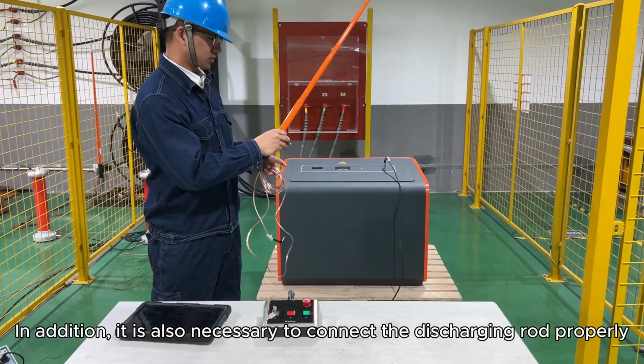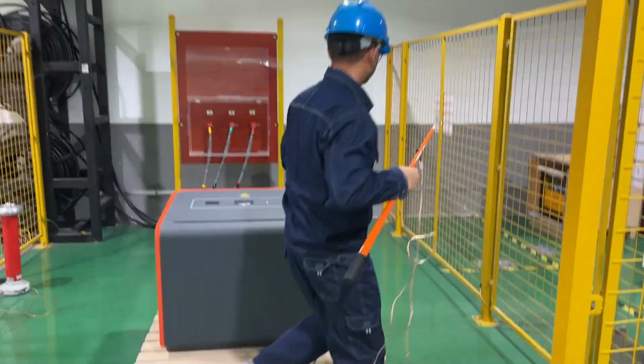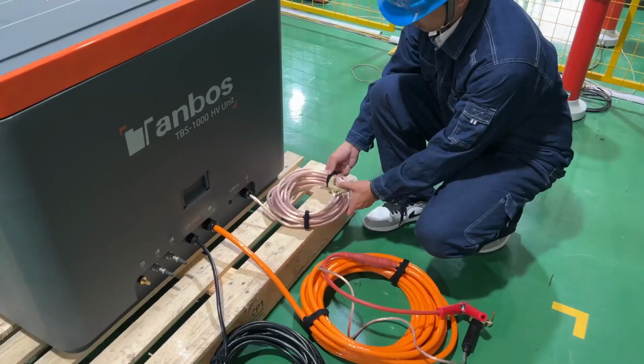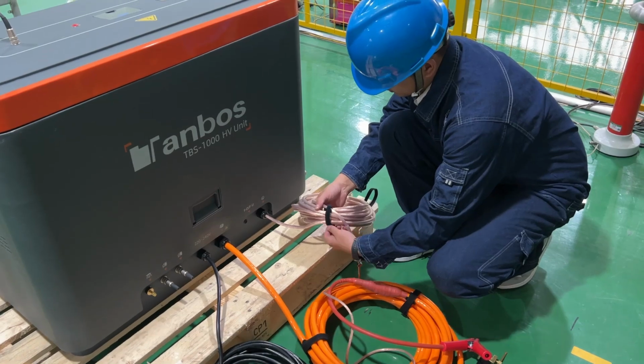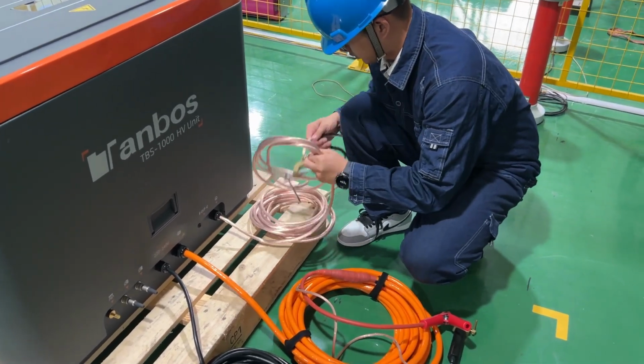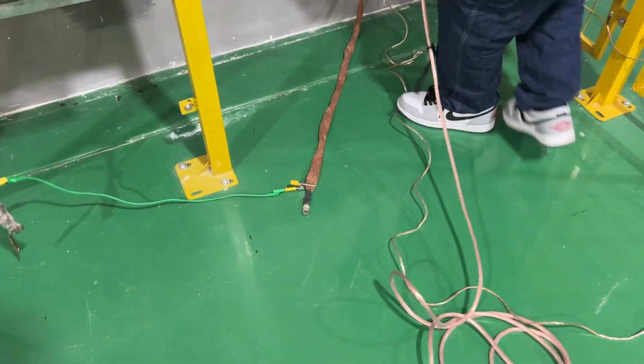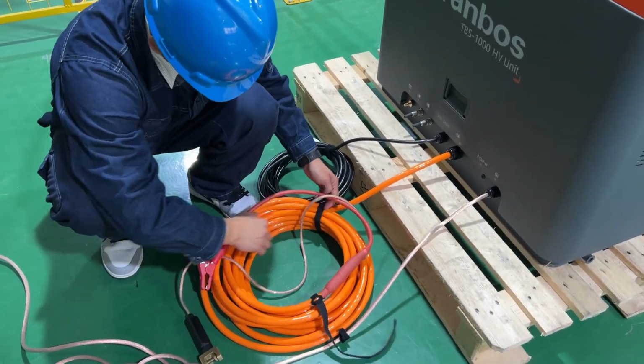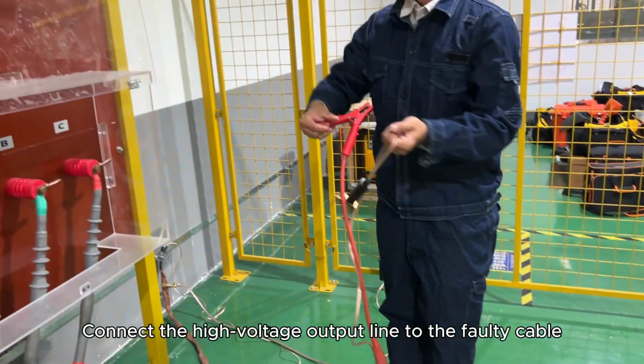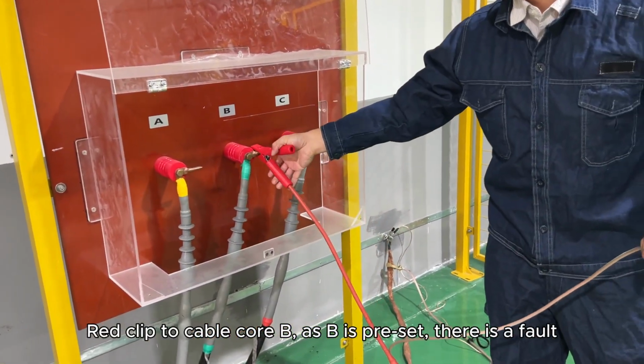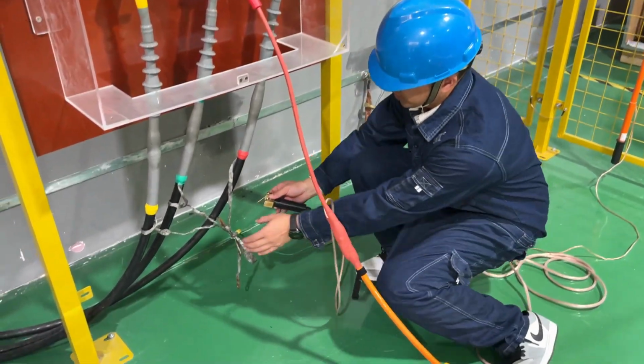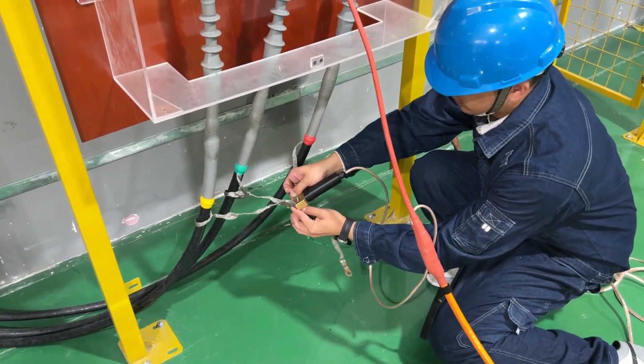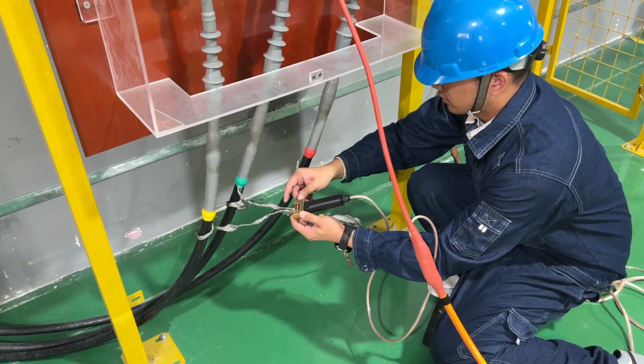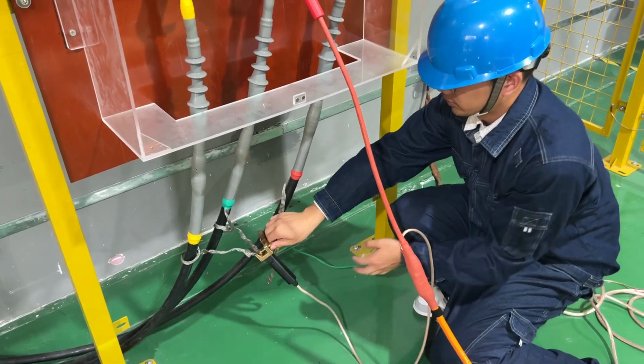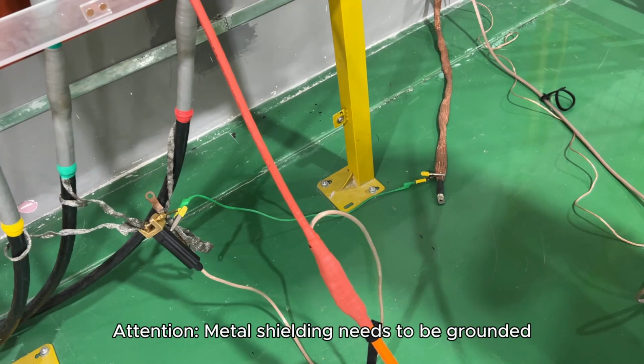In addition, it is also necessary to connect the discharging rod properly. Next, connect the protective grounding wire to the grounding bar. Connect the high voltage output line to the faulty cable. Red clip to cable core B, as B is preset, there is a fault. Additionally, connect it to the metal shielding layer. Attention, metal shielding needs to be grounded.